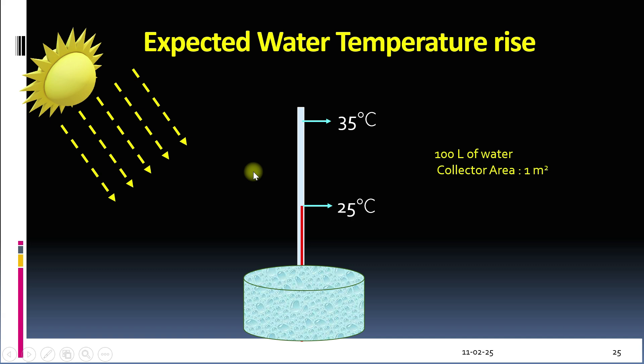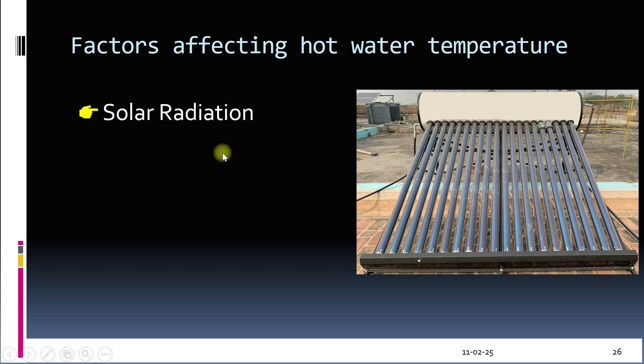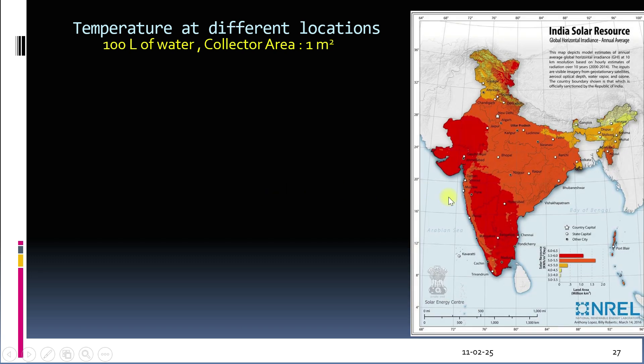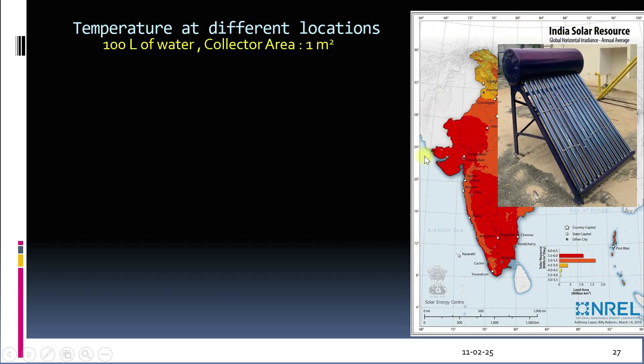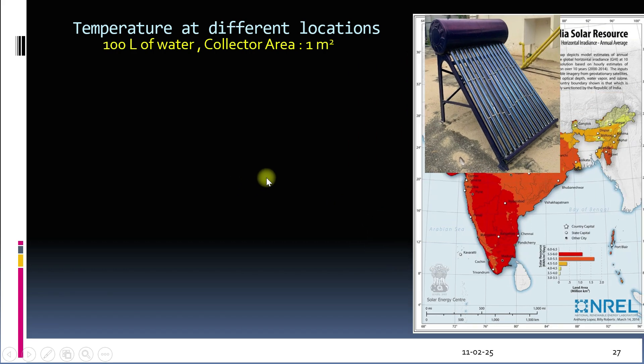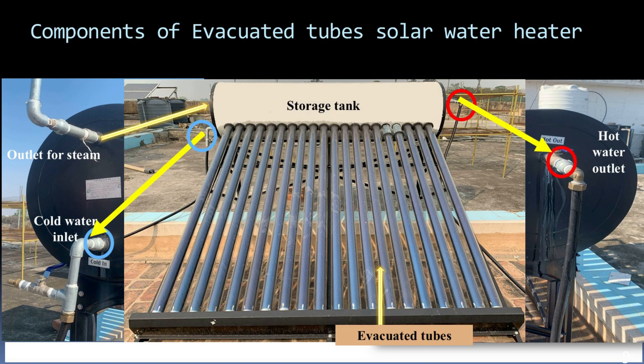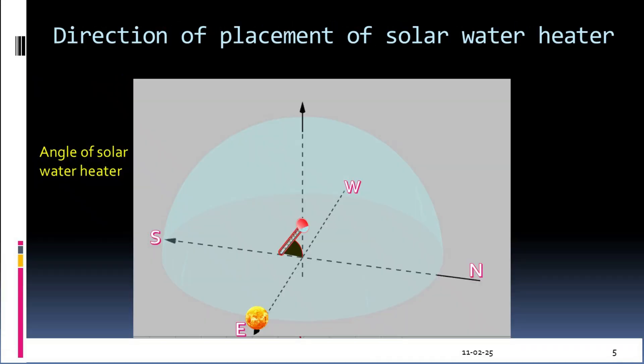The temperature of hot water depends upon several factors. Number one is solar radiation. Number two is temperature of incoming water. Number three is size of the collector area. Solar radiation varies depending upon your location. Areas near the tropics receive more sunlight than other parts of the world. On average, you can expect a temperature rise of 25 to 35 degrees Celsius per square meter of collector area for 100 liters of water in one day. Larger collector areas and optimal angles can result in even higher temperatures.